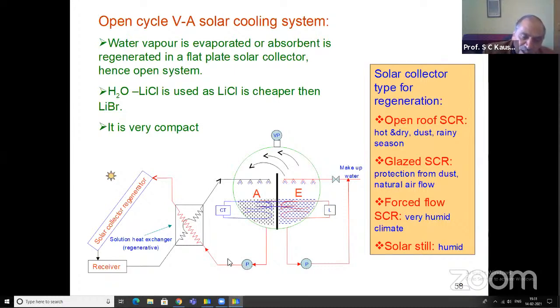Now this solution, which is rich in the refrigerant or water, is preheated through this heat exchanger, and then it is sprayed, with solar energy supplied just by exposing this solution to the sun. Water will be evaporated from this collector regenerator system, and the concentrated absorbent solution is received in the receiver and passed through the solution heat exchanger. Now, rich in absorbent, it is sprayed here, and it will absorb the water vapors coming from here. So the rate of water vapor evaporation in the collector regenerator system is the same as the rate of water vapors being produced here.